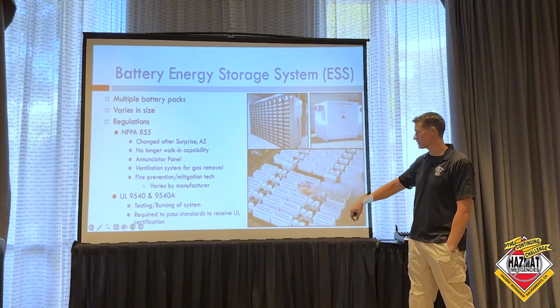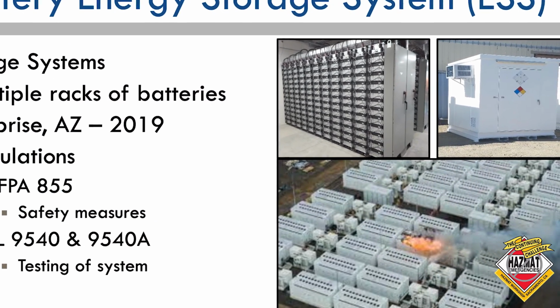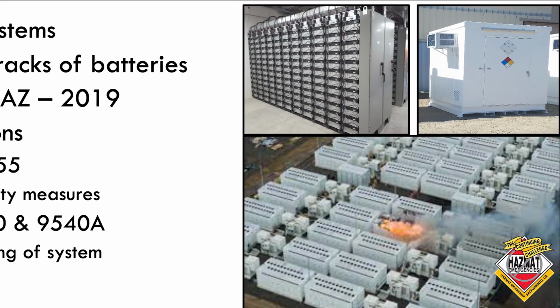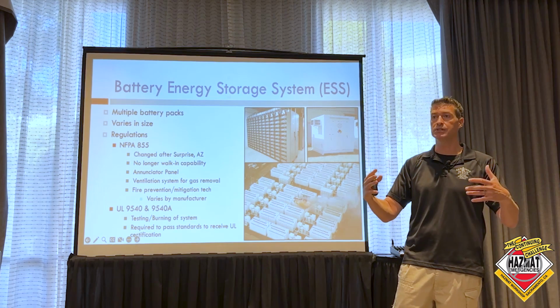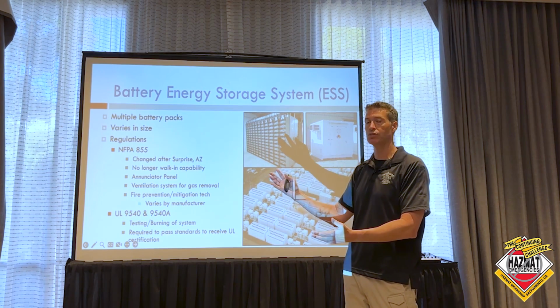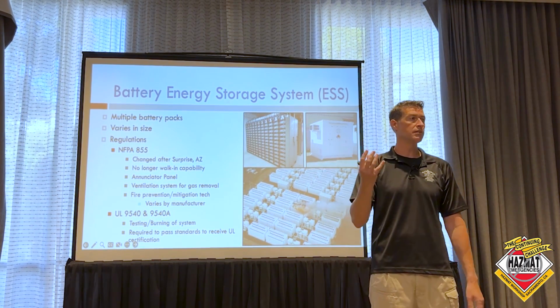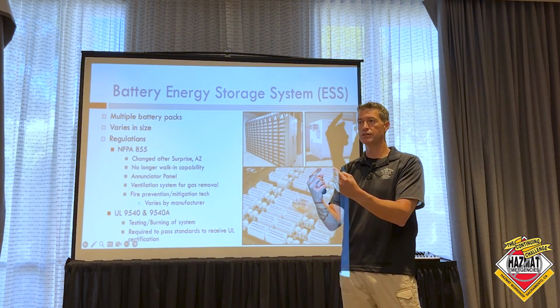This fire that you're seeing out the top, this is the Tesla Megapack. You see all these little black dots on top of the Tesla Megapack. Those are pressure vents. When the batteries start to release their gas, it increases the volume of gas inside that box, and the pressure vents open up. All these toxic gases are lighter than air, right? So hydrogen and HF, they're all coming up and out of that vent. And around that vent, they have sparkers, they catch fire, and then they burn.